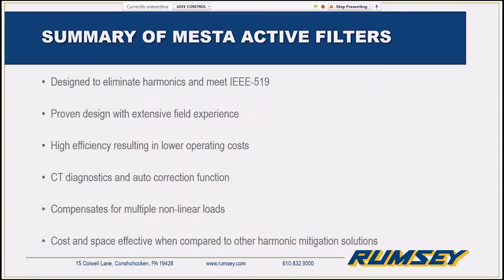But just as a reminder of some of the things as we wrap up this presentation, the active filters are designed to meet that IEEE-519 specification and help to eliminate those harmonic distortions. We have extensive field experience, especially for your applications. It would be really easy for us to get anyone from the factory over to you guys. Very high efficiency, very easy to use with our CT diagnostics, and being able to correct for any number of loads downstream of us.